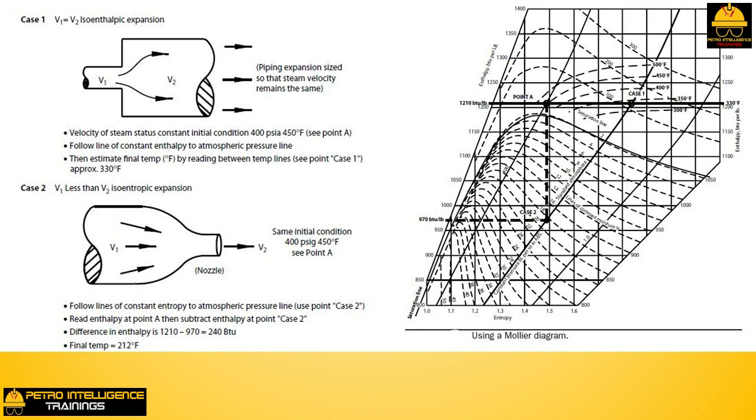Note that the numerical values expressed here are for illustration only, they are not correct in an absolute sense. You may study these concepts and arrive at accurate conversion rates of steam enthalpy to kinetic energy by using the Mollier diagram in your steam tables. Just follow the vertical isentropic lines down the chart from the motive steam conditions down to the exhaust steam conditions. Note the lines of constant moisture as you drop below the saturated steam envelope line.